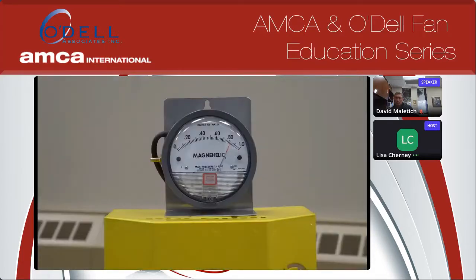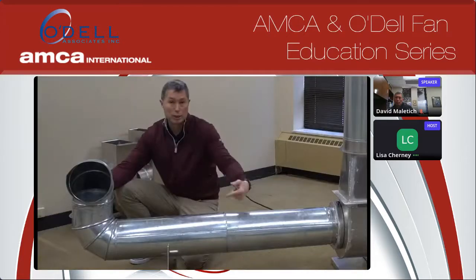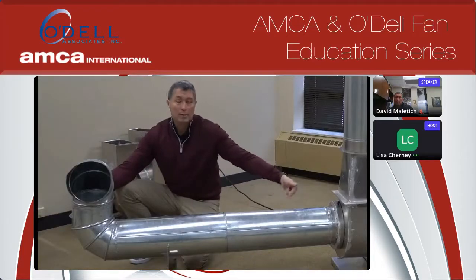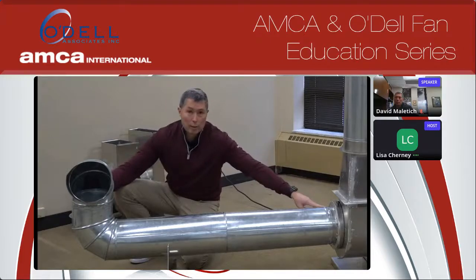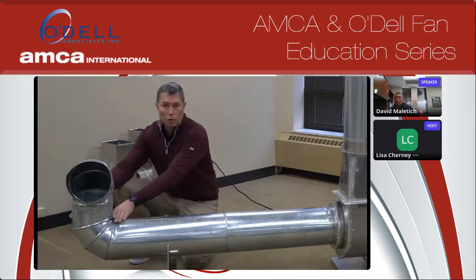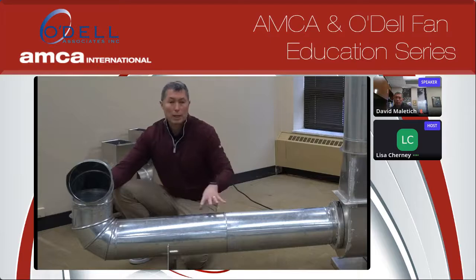And if you look at the Magnehelic, you see that the losses were almost the same as the losses we saw in the first part of the video when we put the corkscrew right at the inlet of the fan. And that's because that air wants to pre-spin all the way down the duct, because the fan's creating a pre-spin, this corkscrew is creating a pre-spin, and there's no place for that pre-spin to go away down this ductwork.